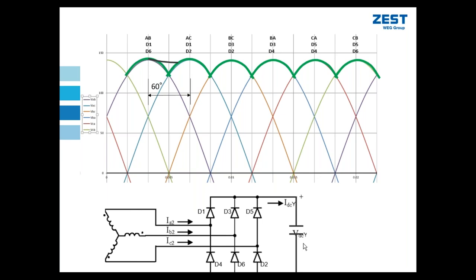We use a capacitor that resists an instantaneous change in voltage. And so the fall off of this voltage is delayed. The capacitor actually holds charge, and that delays the drop off of our DC link. So in essence, what it does is it reduces the overall ripple of that DC link voltage, and we have something that looks a little bit more like the black curve. What's interesting to note, Jay, is I've put two crosses there. Let me just go back a bit.